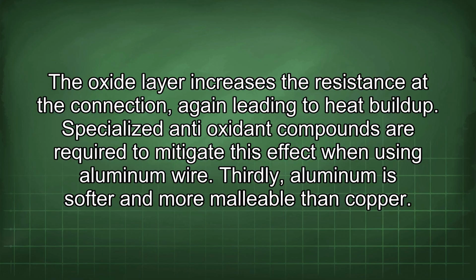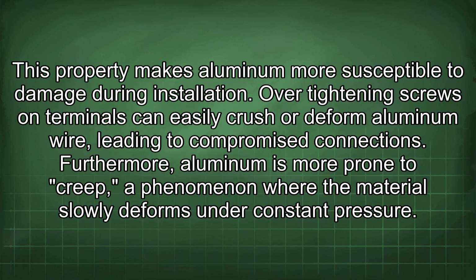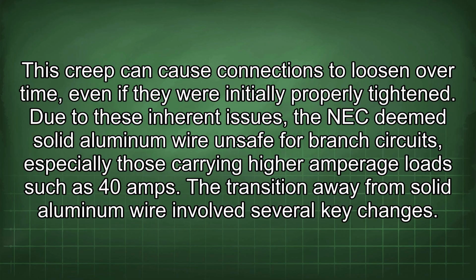Thirdly, aluminum is softer and more malleable than copper. This property makes aluminum more susceptible to damage during installation. Over-tightening screws on terminals can easily crush or deform aluminum wire, leading to compromised connections. Furthermore, aluminum is more prone to creep, a phenomenon where the material slowly deforms under constant pressure. This creep can cause connections to loosen over time, even if they were initially properly tightened. Due to these inherent issues, the NEC deems solid aluminum wire unsafe for branch circuits, especially those carrying higher amperage loads such as 40 amps.